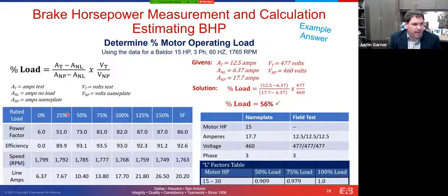So if you look here, this is that Baldor information that we had for this example. You'll notice this is full load amperage, 17.7 amps, which you'll note we pulled off a nameplate over here. And then we have 125%, 150%, and then we have service factor. Service factor is where the manufacturer essentially says not to operate above this range. Normally, you can operate a motor above 100% and up to the point of service factor. It will diminish the life of the motor in the long run, but motor manufacturers will allow you to do it and the code will allow you to do it.